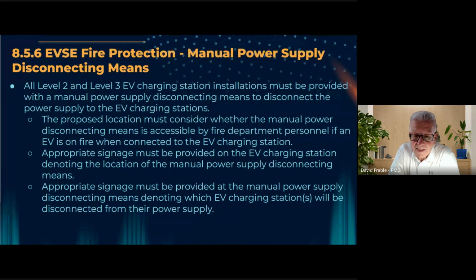These manual power disconnecting means must be in a location for use by fire department personnel or other emergency responding individuals. I would strongly suggest you discuss the possible locations with the regional fire protection engineer and the local fire department or fire code official prior to installing these devices.